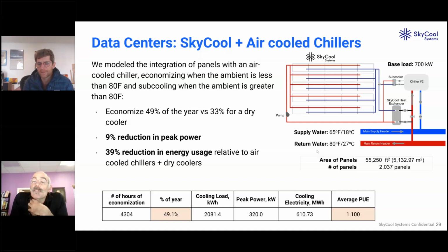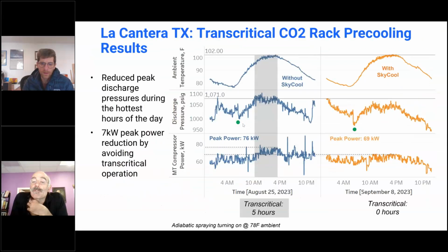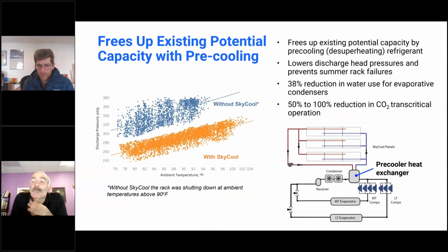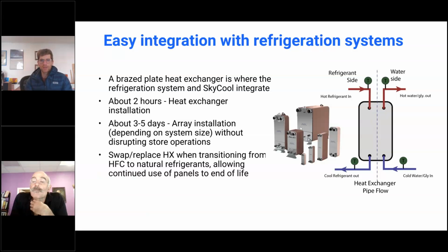Okay, what is the heat exchanger material and configuration for the fluids circulating to the panels? So we use brazed plate heat exchangers. They're manufactured by Alfa Laval, which is a Swedish company, but they're stainless steel typically, and so they're compatible with ammonia. There's high pressure versions which are used for CO2 when you have transcritical CO2 systems. And those are all sort of determined at the point of design when we start a project.